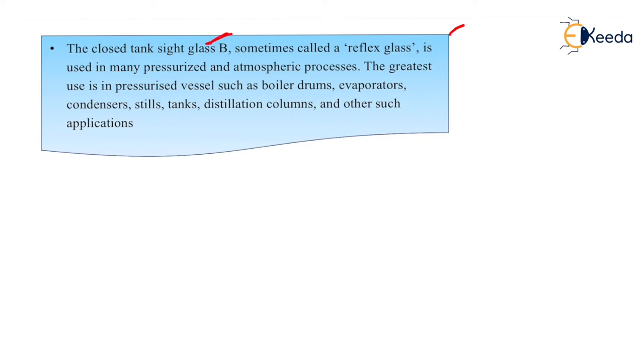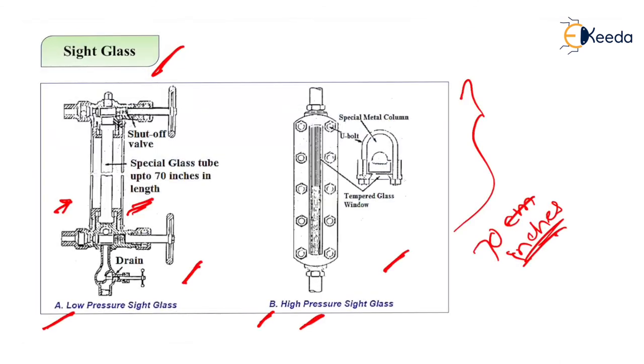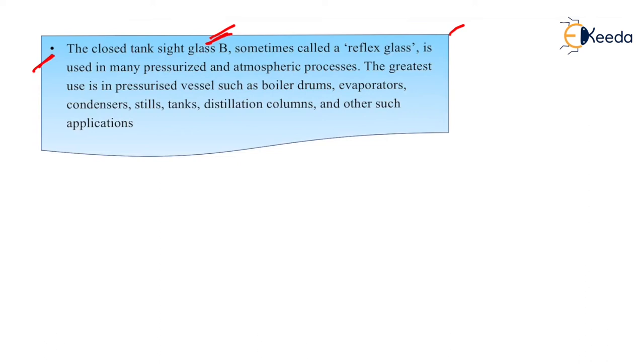Sight glass B is used for high-pressure closed tanks and has a special metal column with a tempered glass window, not present in type A. This closed-tank side glass B is sometimes called a reflex glass. It is used in many pressurized and atmospheric processes, with greatest use in pressurized vessels such as boiler drums, evaporators, condensers, stills, tanks, distillation columns, and other such applications.